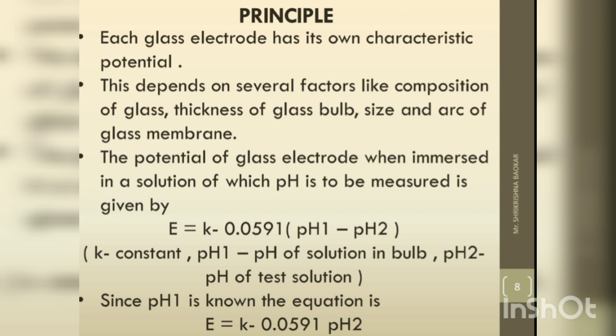The potential of a glass electrode when immersed in a solution of which pH is to be measured is given by: E = K − 0.0591(pH1 − pH2). K is a constant that depends on the nature and composition of the glass. pH1 is the pH of the internal solution, which is known, so the equation simplifies to: E = K − 0.0591 × pH2.